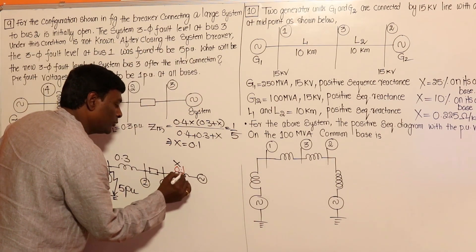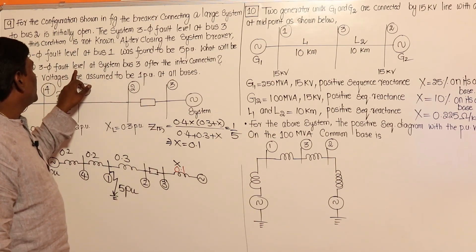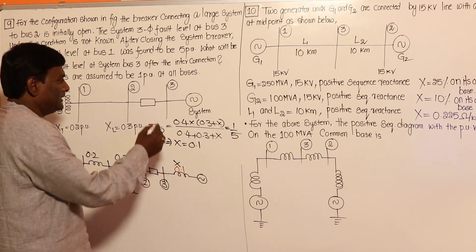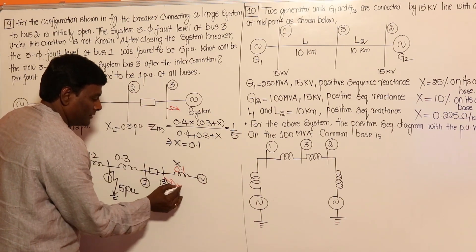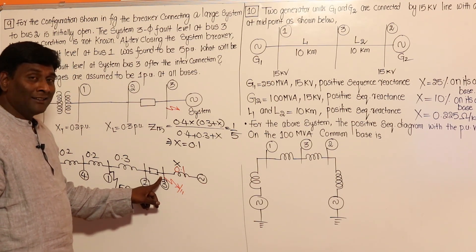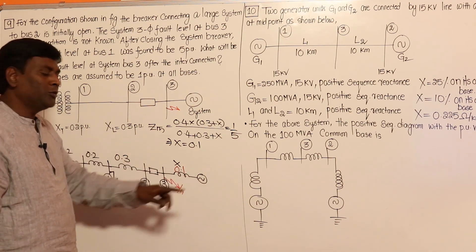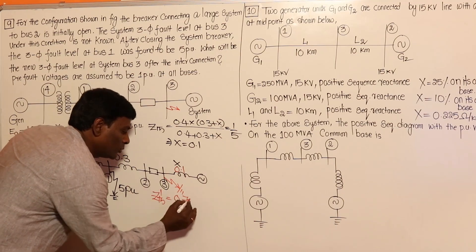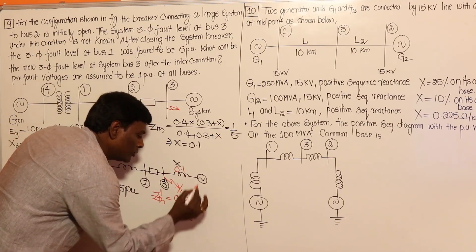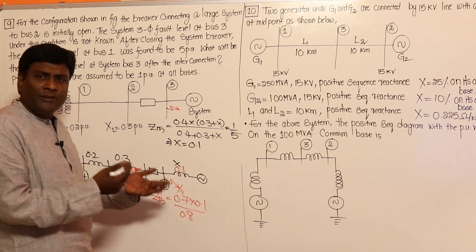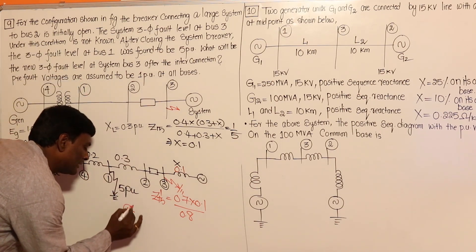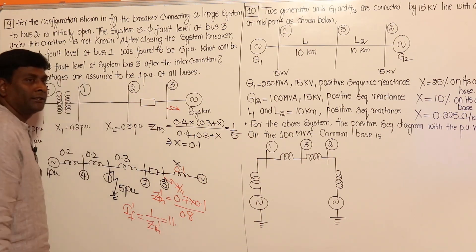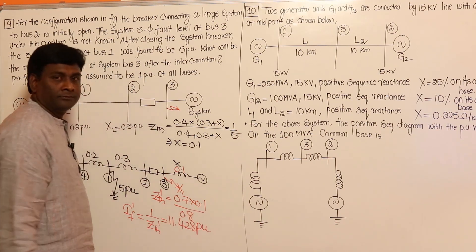With X = 0.1 per unit, for the new fault at Bus 3, the Thevenin impedance is the parallel combination of 0.7 (which is 0.3 + 0.2 + 0.2) and 0.1: Z-Thevenin' = 0.7 × 0.1 / (0.7 + 0.1) = 0.07 / 0.8 = 0.0875 per unit. The new fault current level at Bus 3 is 1 / Z-Thevenin' = approximately 11.43 per unit.